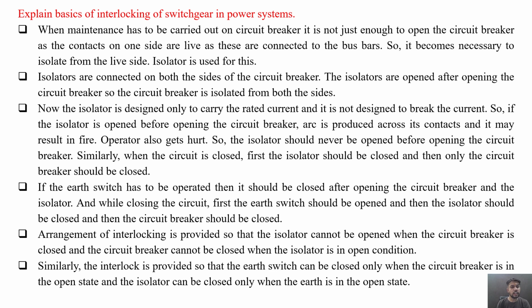An arrangement of interlocking is provided so that the isolator cannot be opened when the circuit breaker is closed, and the circuit breaker cannot be closed when the isolator is in open condition. Similarly, the interlock is also provided so that the earth switch can be closed only when the circuit breaker is in open condition, and the isolator can be closed only when the earth switch is in open condition.